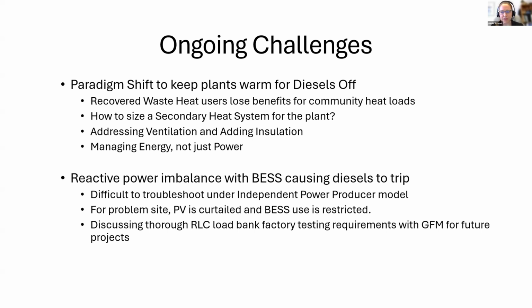Finally, we've had some issues on some of the systems, specifically the PV BESS projects done through an independent power producer. We've seen reactive power imbalances affecting our diesels, and that has become really difficult to troubleshoot. So we're left wondering how we can front load this with rigorous factory testing using a reactive load bank, and really get some baselines established, because once it's installed in the field with variable loads feeding customers in a very remote location, it's difficult to go back and troubleshoot these systems. How can we be ahead of that in future projects?